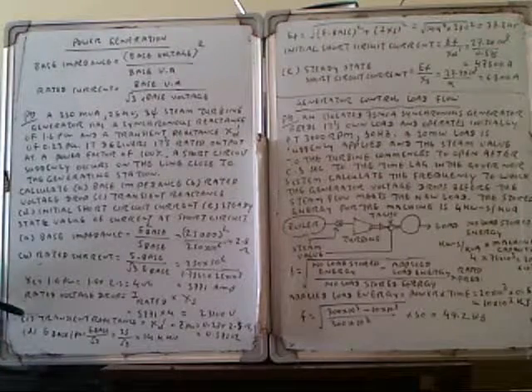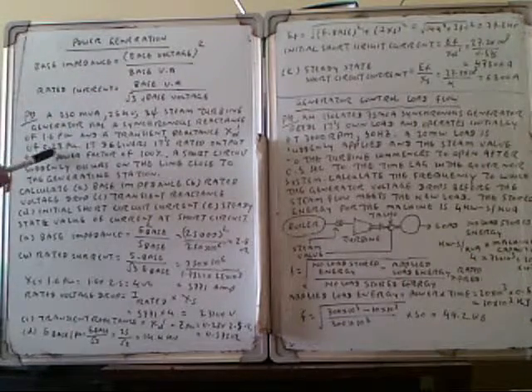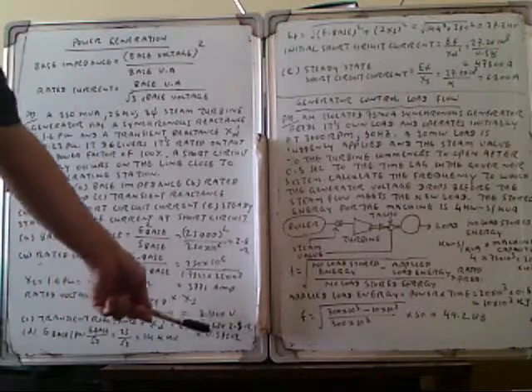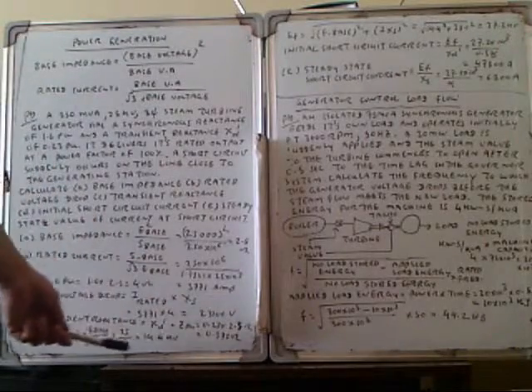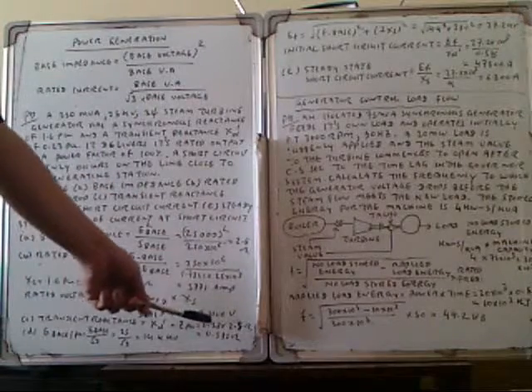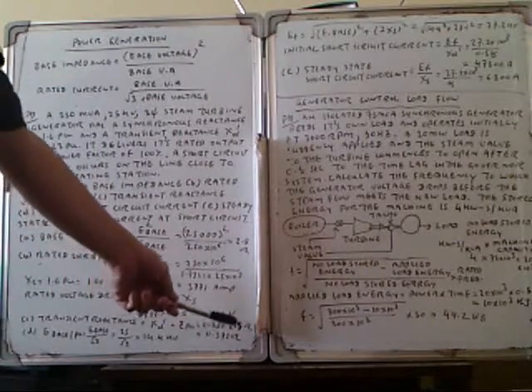The transient reactance can also be calculated. The transient reactance is 0.23 per unit. Since 1 per unit equals 2.5 ohms, the transient reactance is 0.23 × 2.5 = 0.575 ohms.